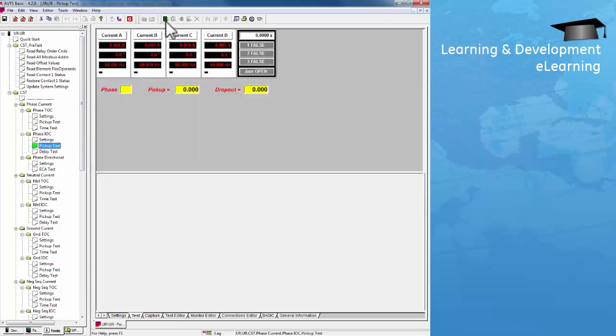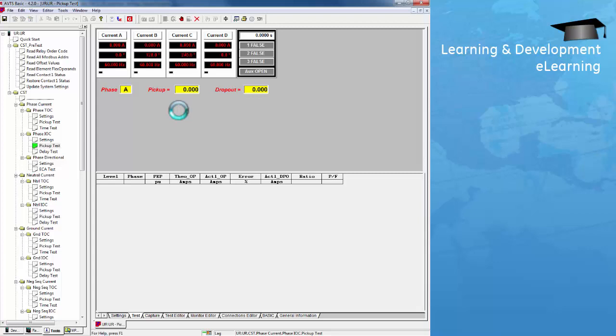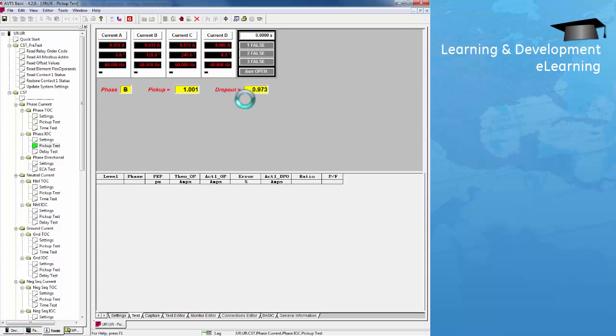Now I'm going to run the pickup test. The first test is on phase A — current is injected into the relay starting from 95% of the pickup value. The increment is 1mA for this test. We can hear the relay operated; the pickup is 1.001 for this 1PU with a 1A CT. The test is now running for the dropout. Phase A is done and now it's testing phase B.